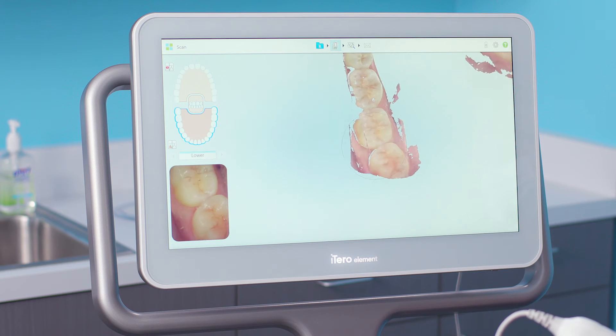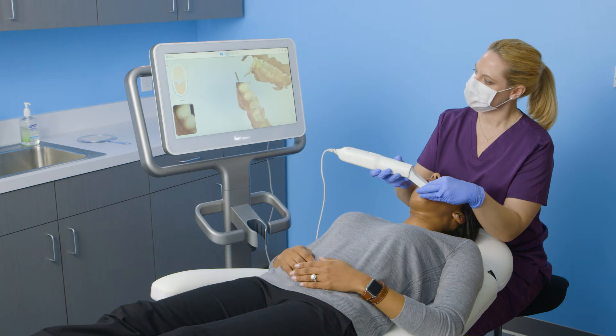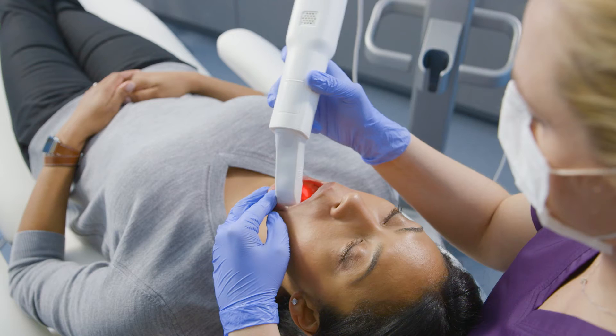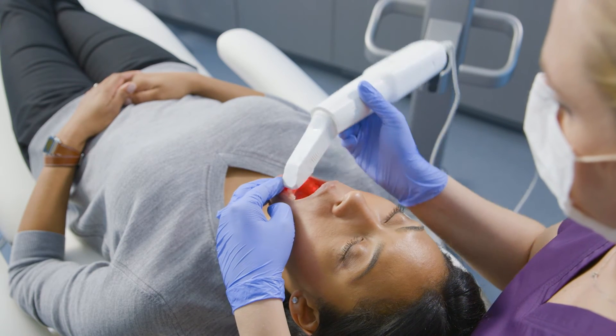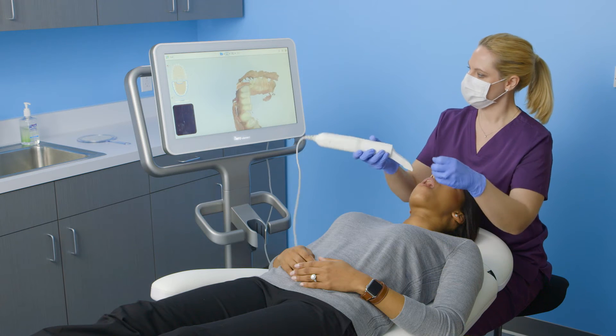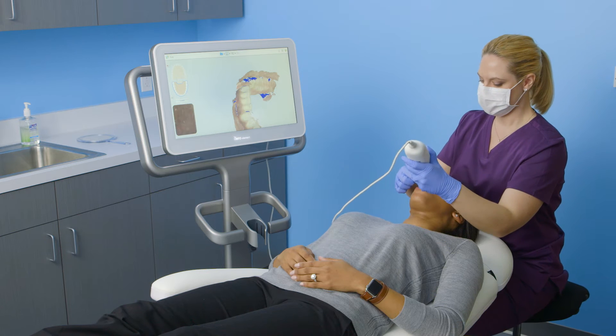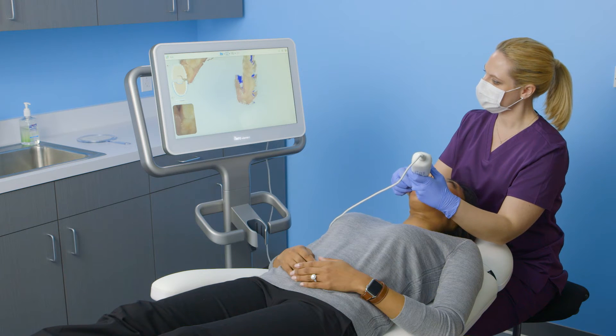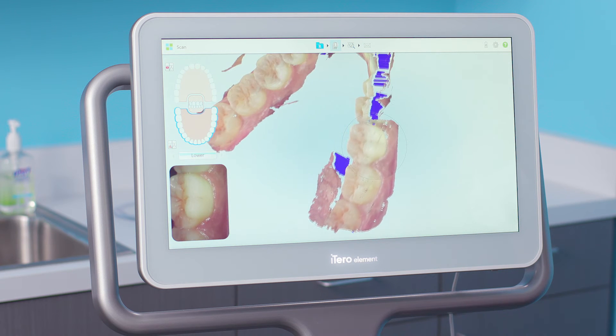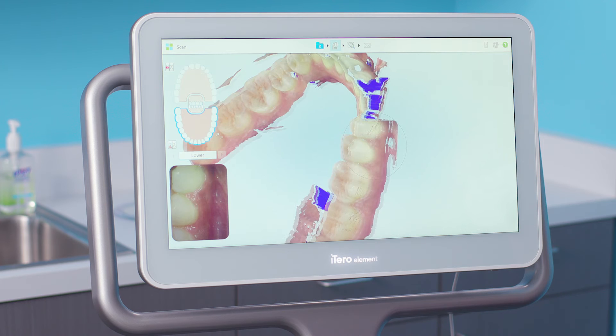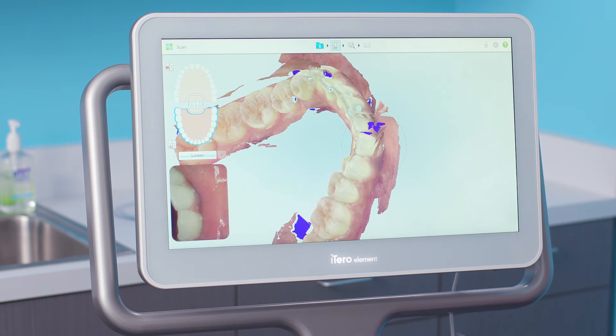After I have completed the lingual, I'll rotate to the buccal and use a rocking motion as I move toward the anterior to capture the inner proximal anatomy. When I cross the midline, I'll move the wand tip toward the opposite terminal tooth and use the same rocking motion to capture the buccal surface from the posterior to the anterior. Moving from posterior to anterior when scanning the buccal surface reduces the interference from the cheek and provides a smoother scanning experience.